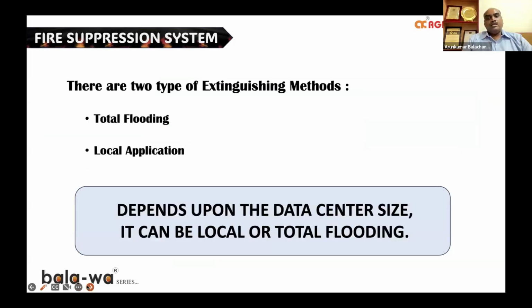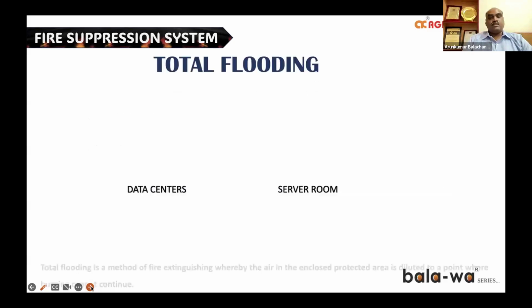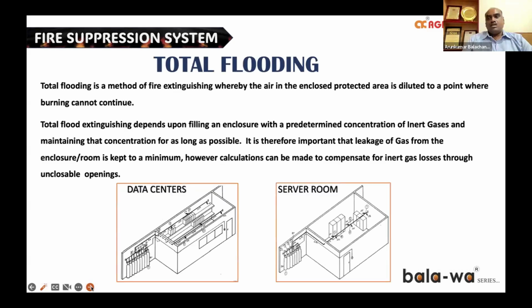The inert system can be designed in two different methods: total flooding and local application. The method depends on the size of the data center and the locality of the data center. In the total flooding method, what we are aiming to do is bring the oxygen content of the entire risk room from 20% to less than 15%. That is our aim in a total flooding inert system. Because of this, the room should not have any unclosable openings, so that 85% of our design concentration is maintained for the next 10 minutes, so that complete suppression can turn into extinguishing capability.